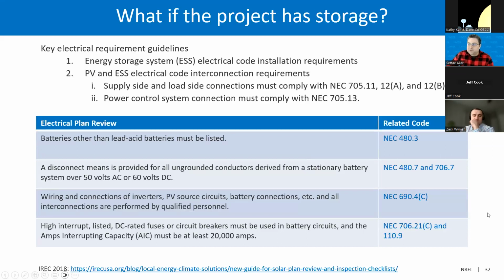So when we come to the stage where the project has storage, what are we going to do when we have a project which has storage? There are additional requirements and guidelines to follow. If the project has an energy storage system, the plan review would be subject to additional code installation and interconnection requirements. The supply side load connections must comply with the National Electrical Code 705.11 and 12A and 12B.